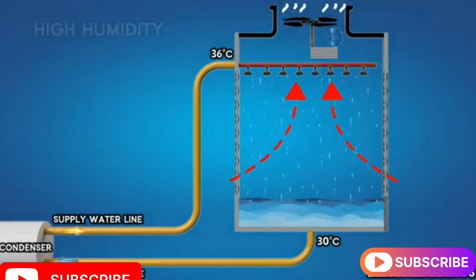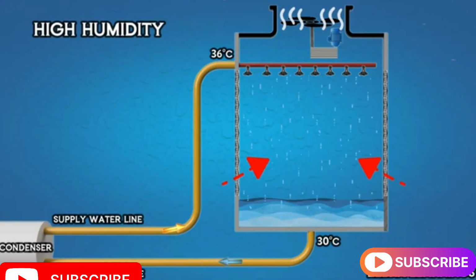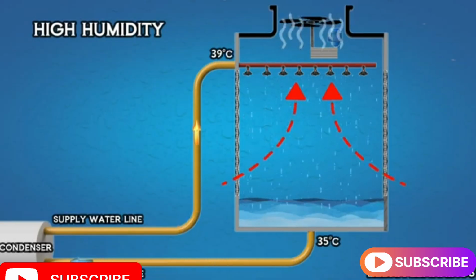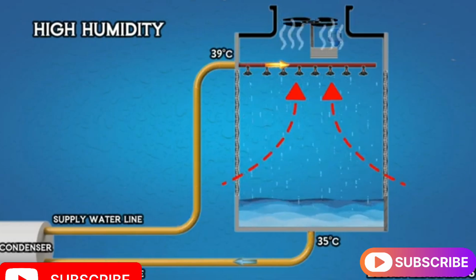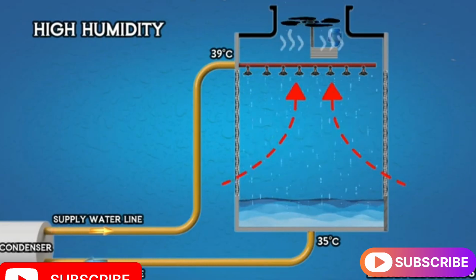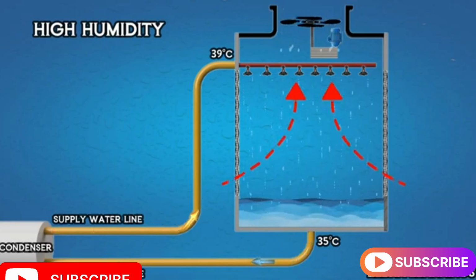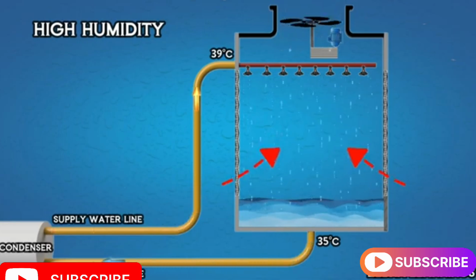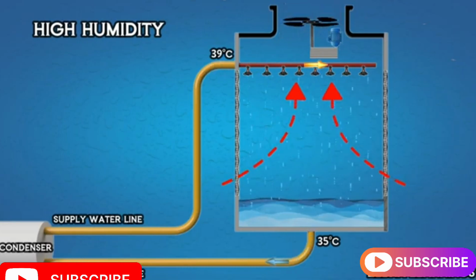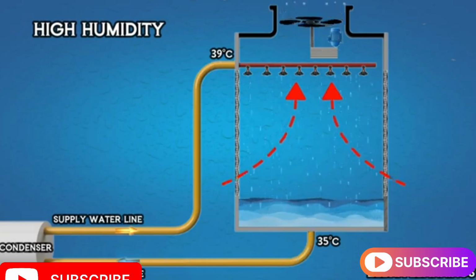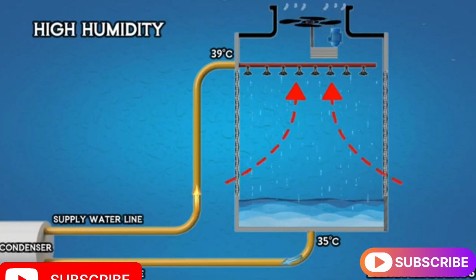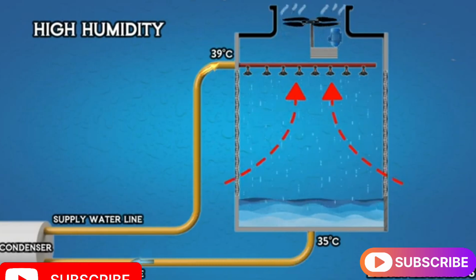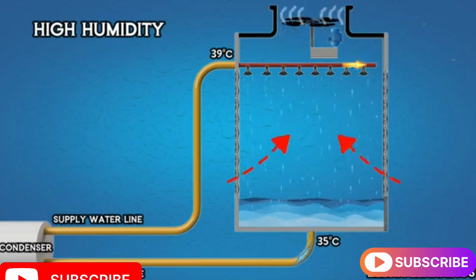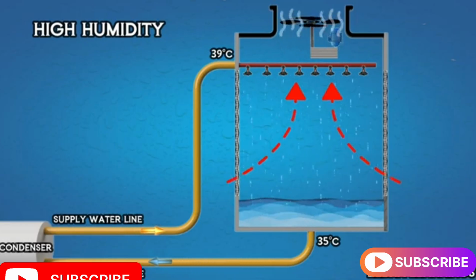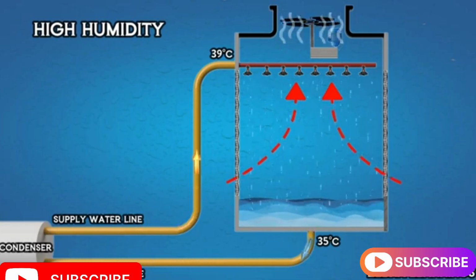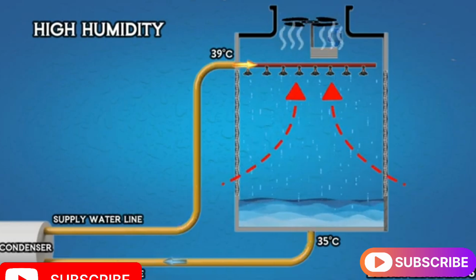However, when the humidity level is high, less water evaporates from the cooling tower, and the water returning to the chiller is not cooled as effectively. This reduces the cooling tower's efficiency. Since the water entering the condenser is at a higher temperature due to the high humidity, it cannot cool the refrigerant as effectively. This leads to an increased load on the chiller. This is how high humidity affects the overall process of a chiller plant.